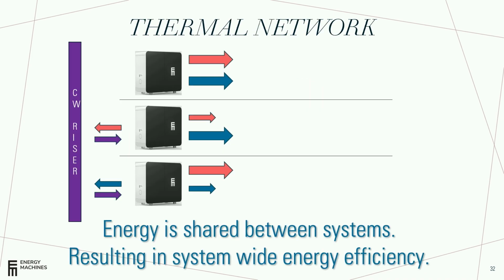And so with this solution, now you have systems that are in excess cooling feeding systems that are in excess heating. You can extract heat from one floor, have your energy arbitrage in the condenser water riser, and you're essentially dropping those BTUs somewhere else that you actually need. So energy is shared between different systems, different floors, it's all connected, and you basically have a system that results in a much higher efficiency than you would otherwise trying to solve that in the box.